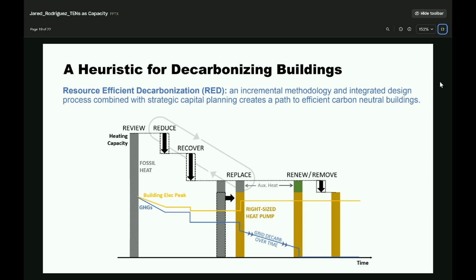Recover heat. There's a myriad of ways to recover heat leaving the building, like in the wastewater stream. When you take a shower and it goes down the drain out to the sewer, that water's leaving the building at 90 degrees. It passed by your body in 3 seconds or less. Is that a good utilization of heat? No. Try to get the heat back before it leaves the building and make new domestic hot water or space heat.